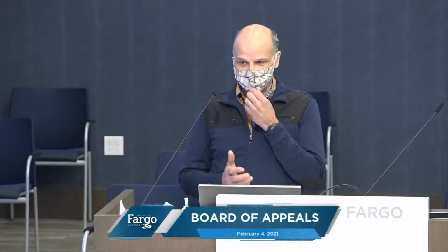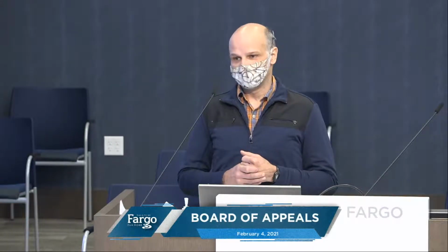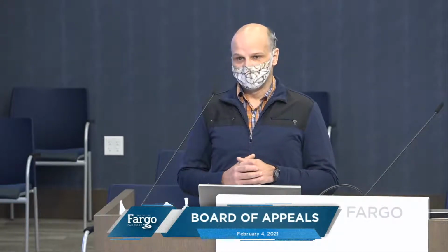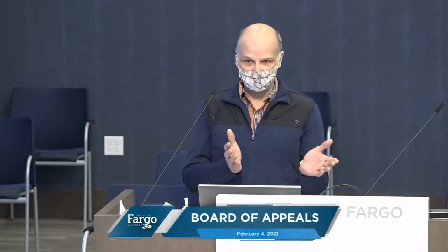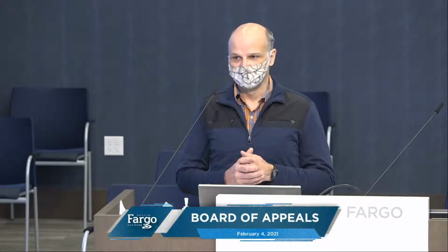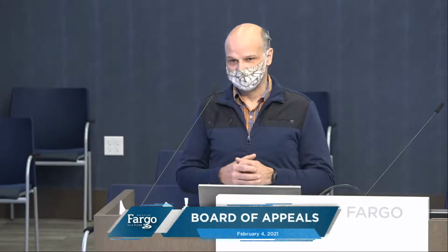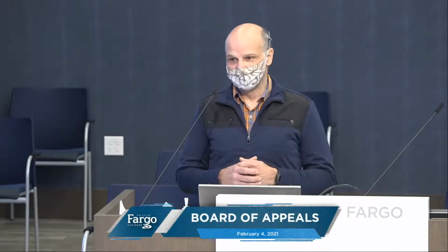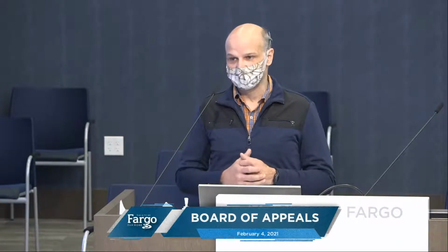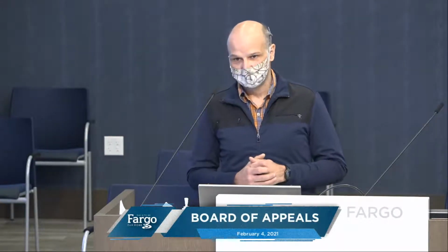So we're asking this board to look at the specifics of 508 and recognize that, for one, there is no separation requirement between U and S2 in any situation, regardless of how one might interpret footnote B to be applied, and that those specific requirements of 508 shall be applied over the more non-specific or general definition provided in 406.3.1.